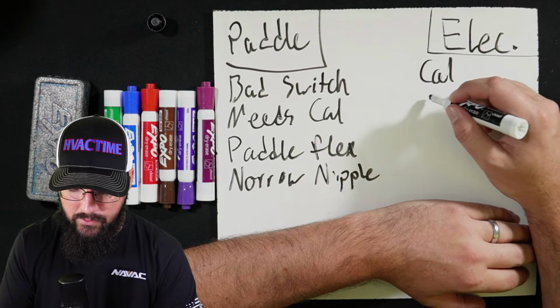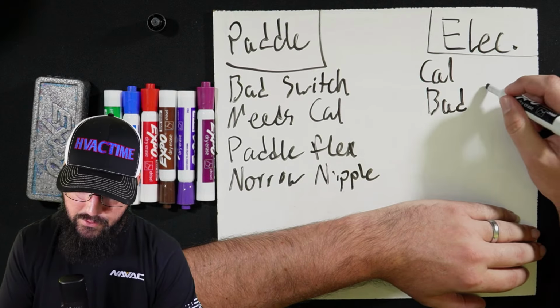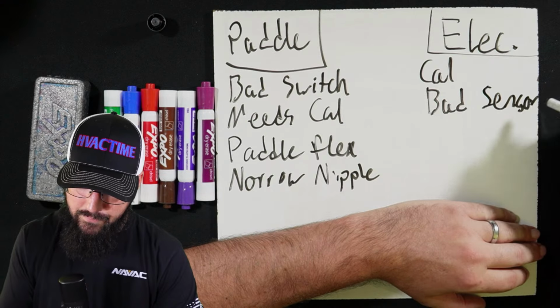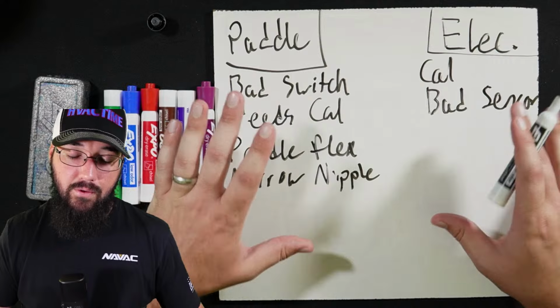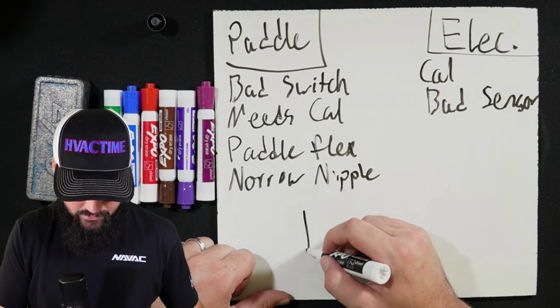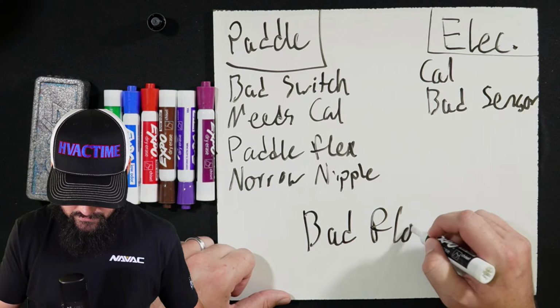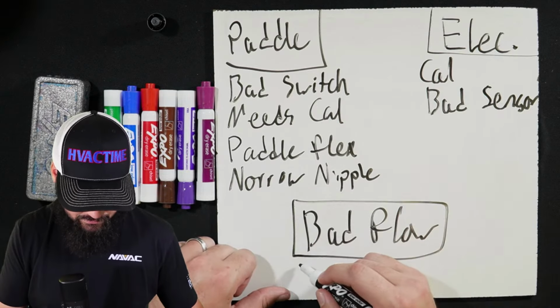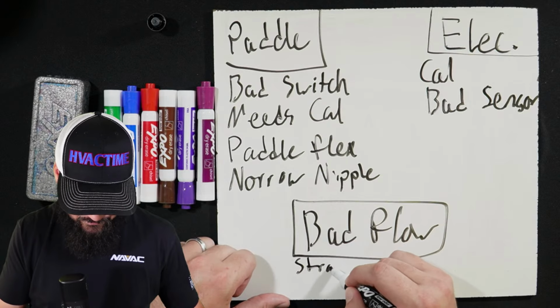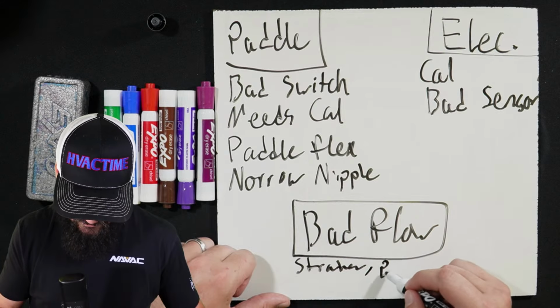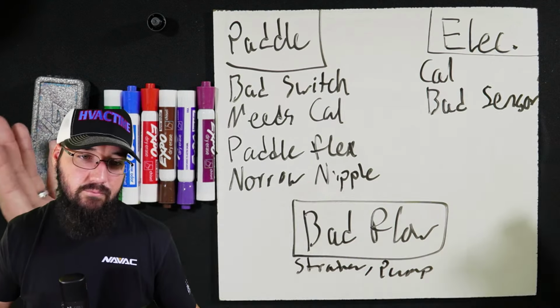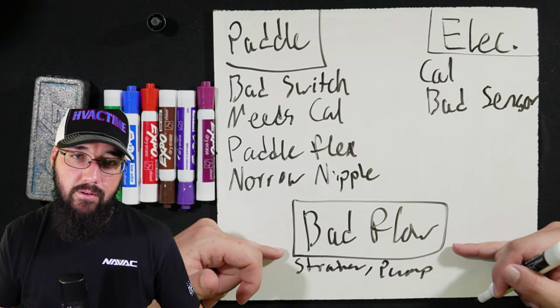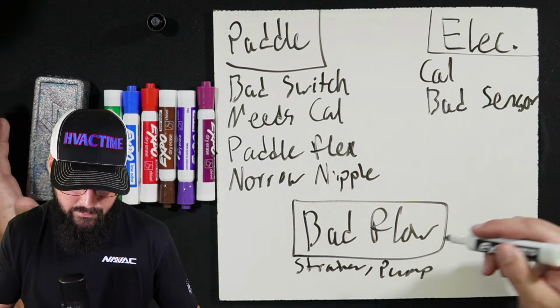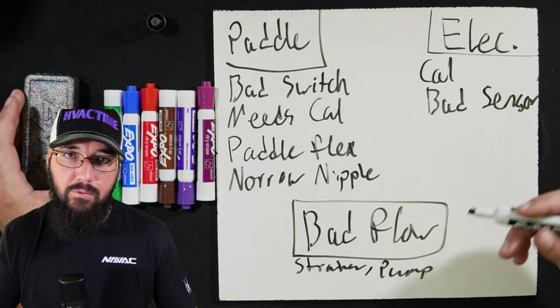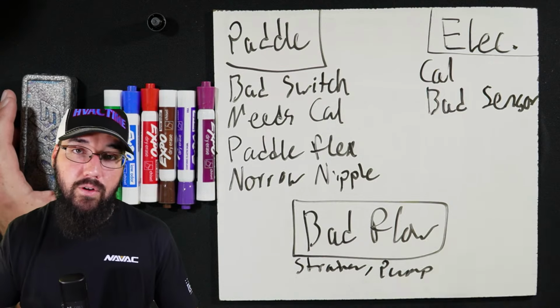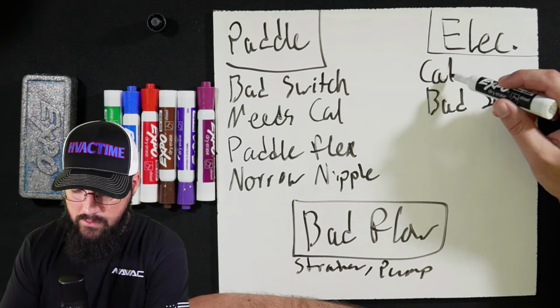It could be a bad sensor, all right? So the sensor itself could be just bad. One thing that could be true for both of these is just bad flow, which may be a strainer issue, could be a pump issue, whatever the case may be. We could just have bad flow, by the way. Like in all of this, check your strainers, check your valves, make sure your pump is actually moving water the way that it needs to. Okay, so back to electronic flow.